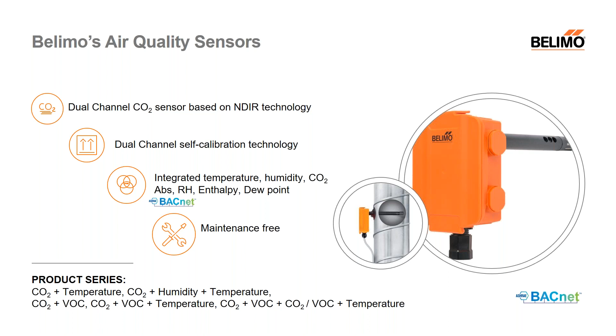So what exactly entails Belimo's dual channel calibration technology, and why and how is it different than the standard technology used to detect CO2 levels? Well, within CO2 sensors in general, there's typically a single detection element incorporated with a type of gas concentration correction software, which is otherwise known in the industry as ABC logic. This software typically assumes that CO2 levels in non-occupied spaces is roughly 400 parts per million. So as this sensor takes its measurements, this 400 parts per million value then offsets the CO2 measurement in an attempt to achieve more accurate readings.